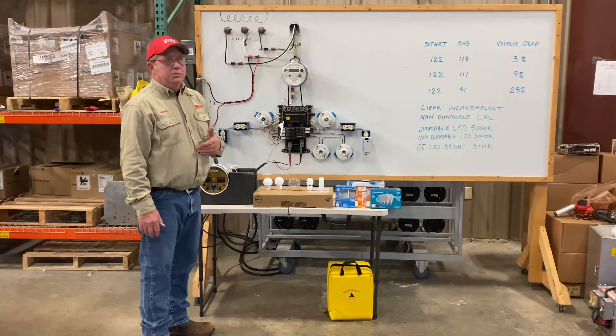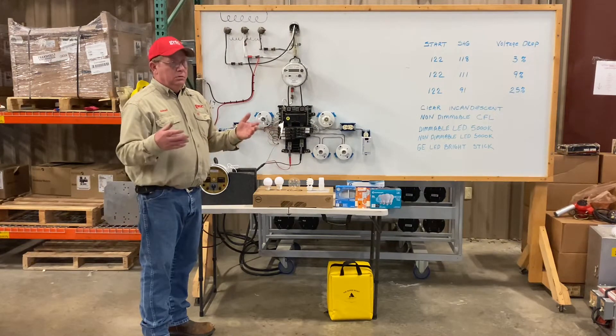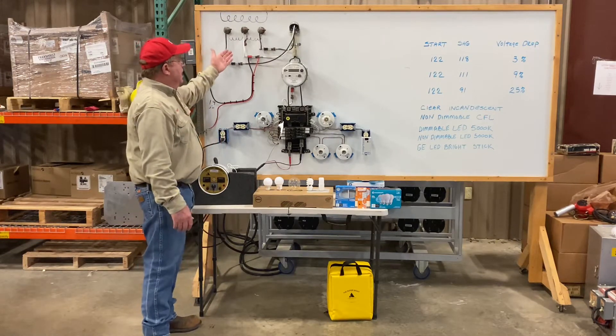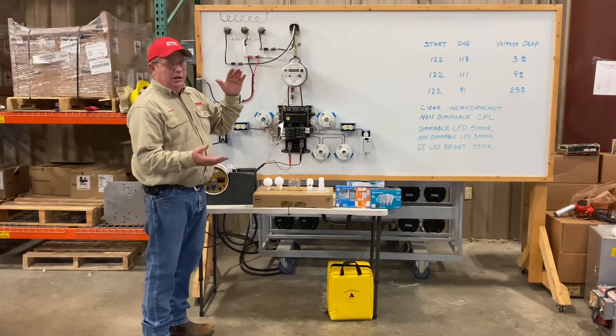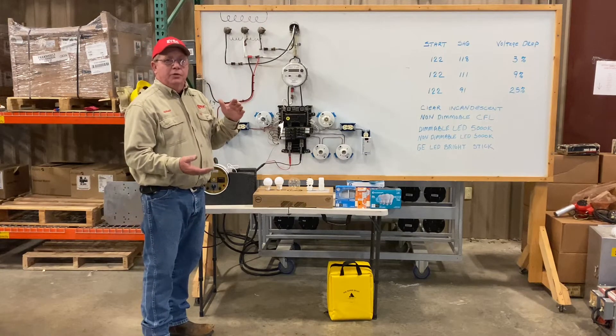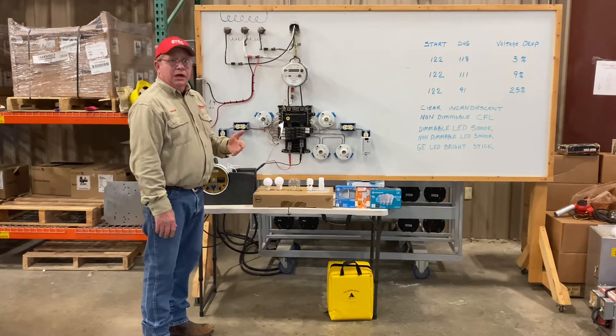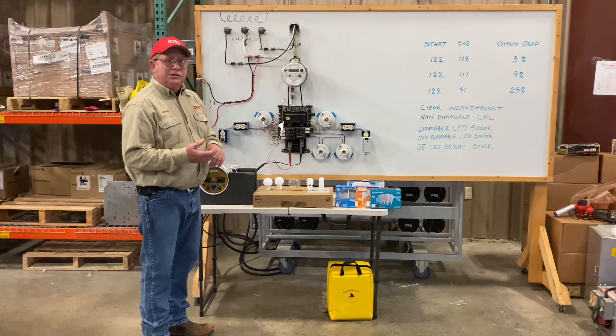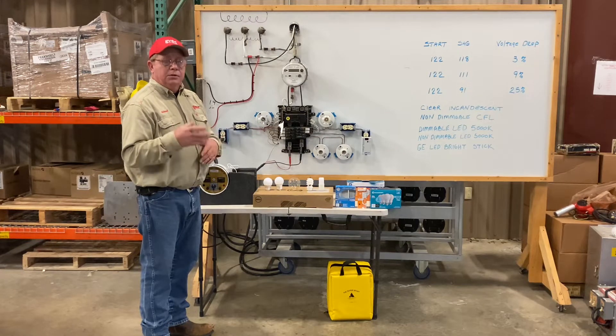Today, we put a lot of primary loops on transformer poles, and we control our voltage drop so that we only have the voltage drop from the transformer and the voltage drop in that 20 feet of wire in the riser before it gets to a meter socket. Past that, the customer has his underground length, his load, and his wire size — those are the factors of voltage drop that he sees.